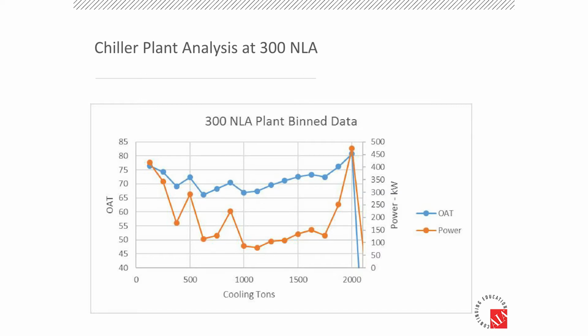So breaking it all down, all the weather data is at hourly level. So breaking it all down, we could actually see where the chiller needed to be upgraded. Which chillers could do the job, which ones couldn't do the job. We have this per machine. This is actually the aggregation of the whole plant. What surprised me is that it really doesn't care about what the outside air temperature is. It's a function of time of day, and it's a function of how many people are in the courthouse.